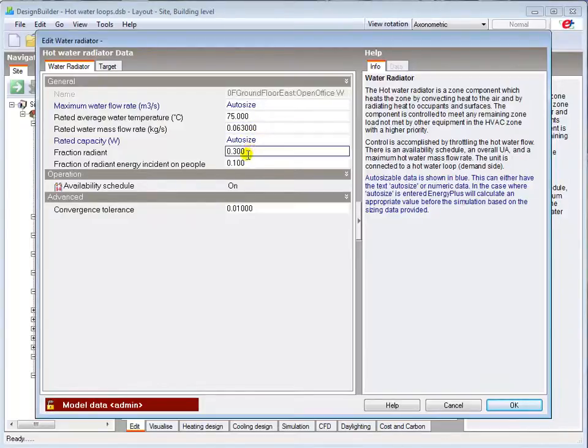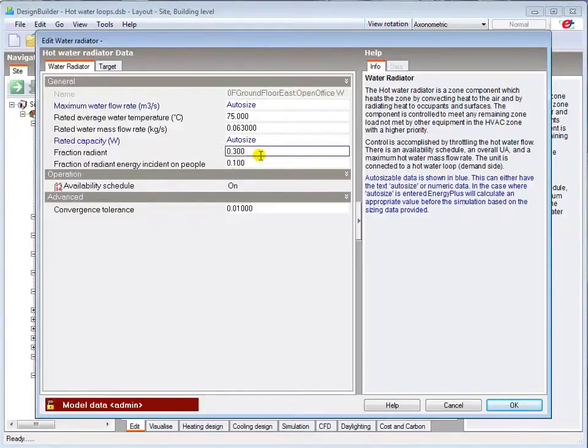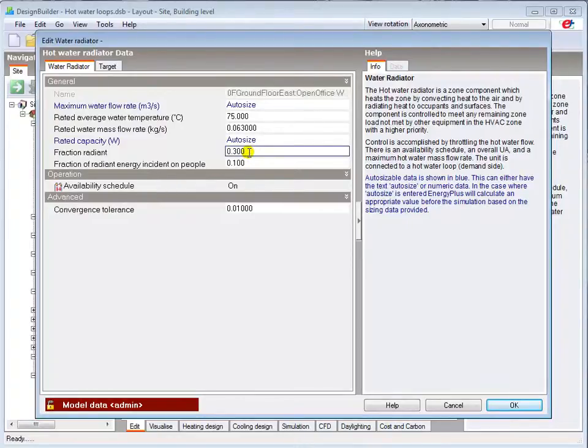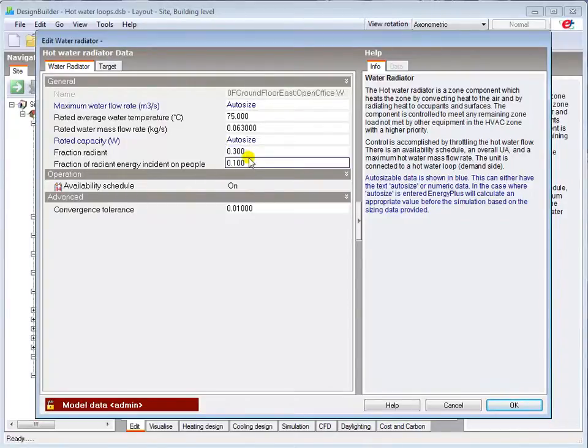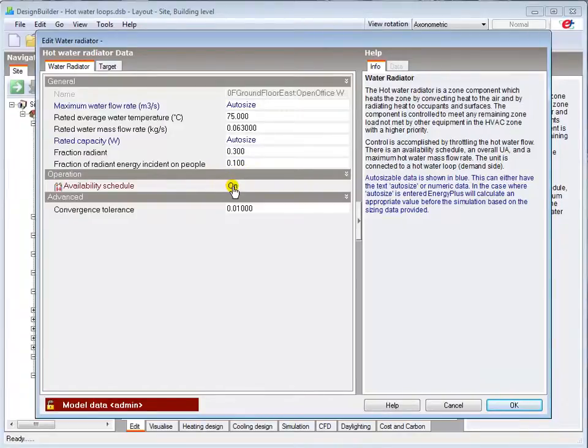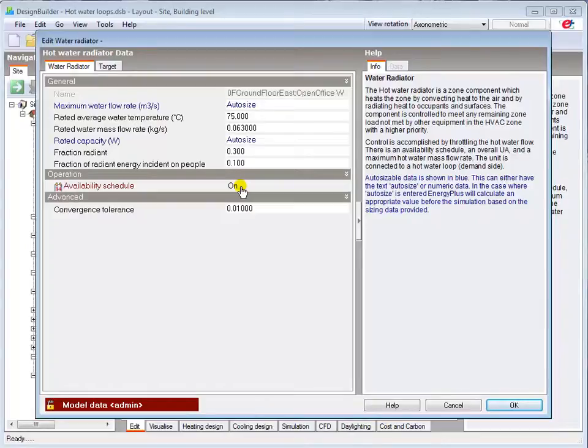Again, the radiant fraction defaults are a reasonable starting point. Many people are surprised at just how low the radiant fraction is for a component called a radiator. The component is scheduled on by default, so it will always be available to meet a demand placed on it, providing it's receiving hot water from the loop.